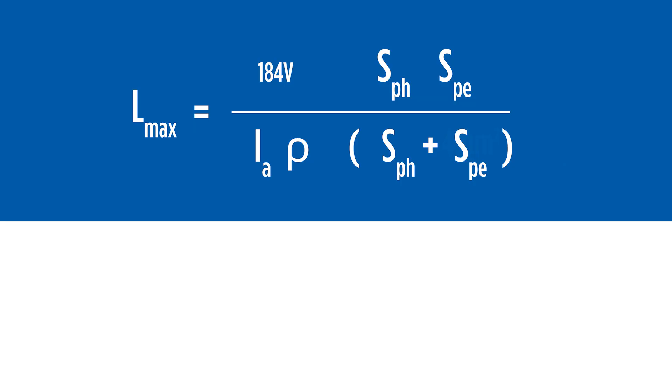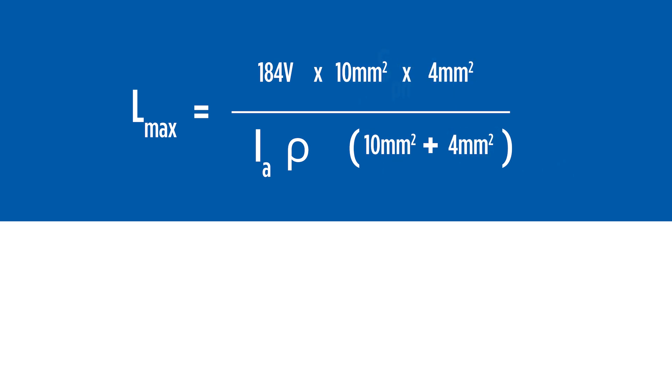When considering cables of 4 millimetres squared and above, earthing conductors will have a smaller cross-sectional area than the active conductor. As an example, a 10 millimetre squared cable will have a 4 millimetre squared earth wire.